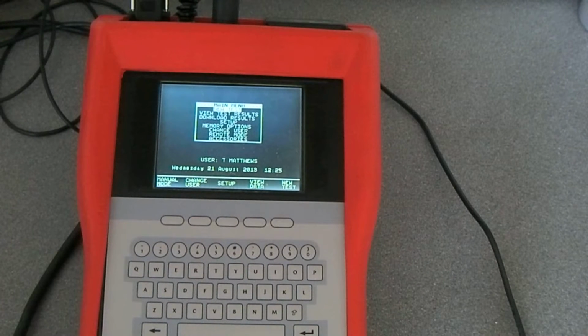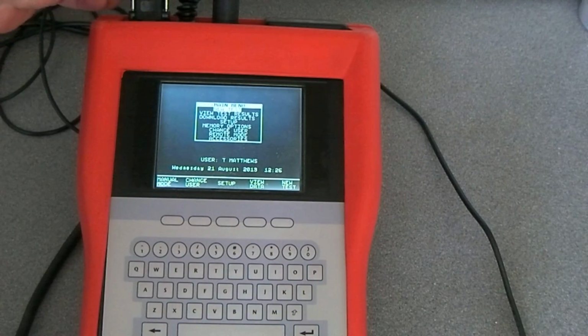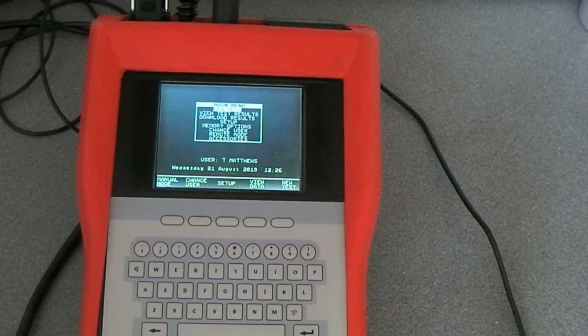But I'm taking on something on a more commercial basis where most of the repairs will be changing mains leads and mains lead sockets. So I had to get a PAT tester to comply with the rules and regulations. You can buy brand new PAT testers obviously on eBay. £300 to £400 would get you a reasonable one, but really what I wanted was some sort of data logging facility, so the test results can be downloaded onto the PC and then you can print out certificates and that sort of thing if required. So having had a look around on eBay, I came across a seller.